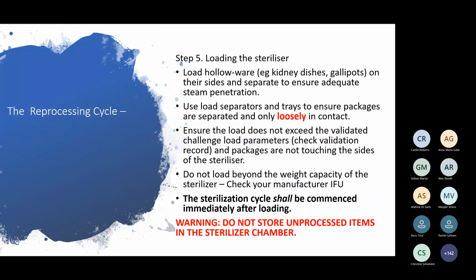So, loading the sterilizer: load hollowware, kidney dishes, whatever, on their sides and separate to ensure adequate steam penetration. So please don't have them stacked on top of each other. Use load separators like your toast racks and trays to ensure packages are separated and only loosely in contact. Never stacked, never two layers of instruments, only a single layer, please.